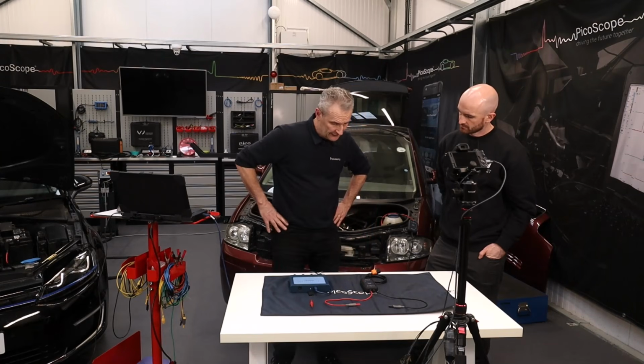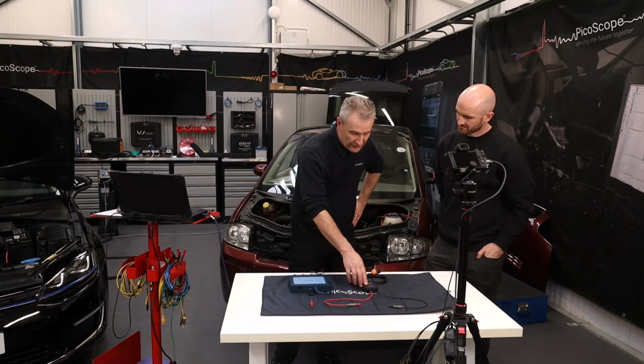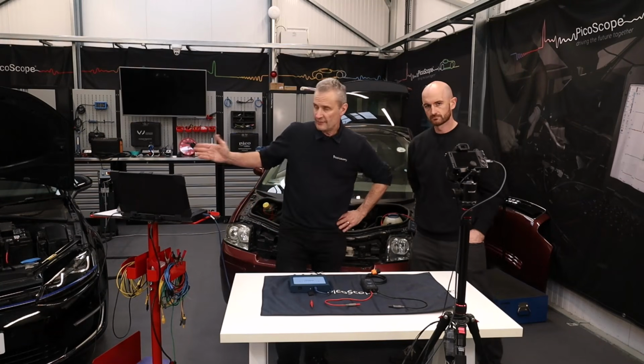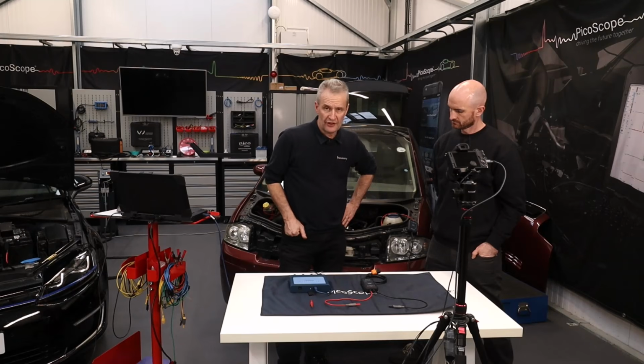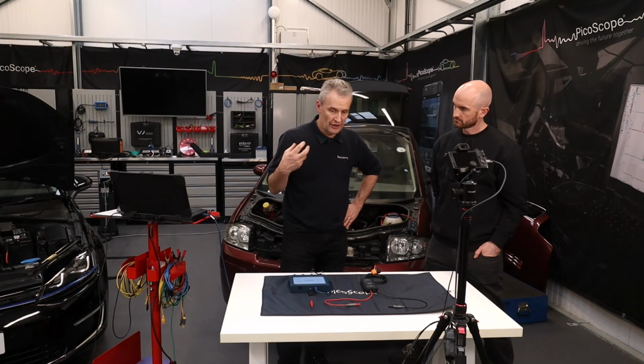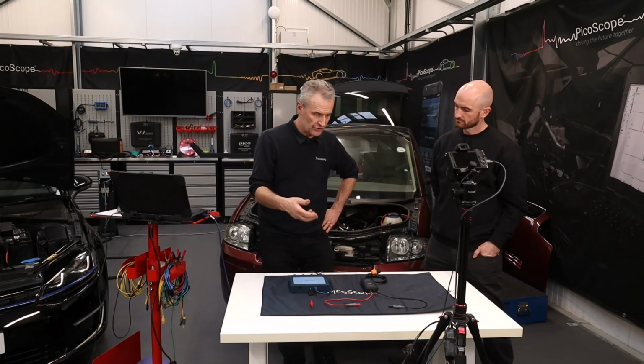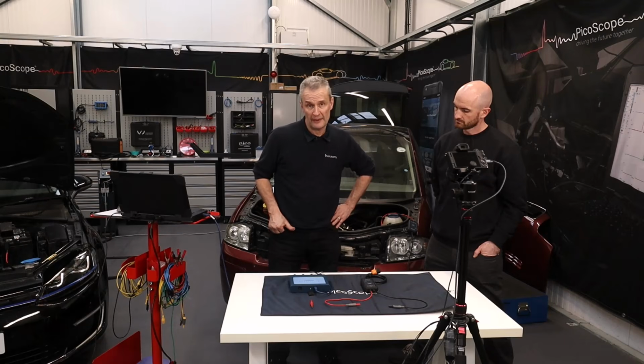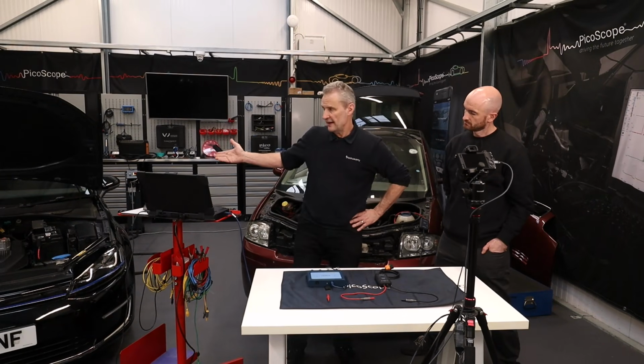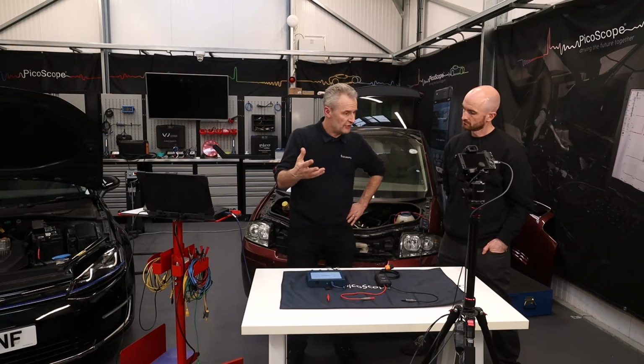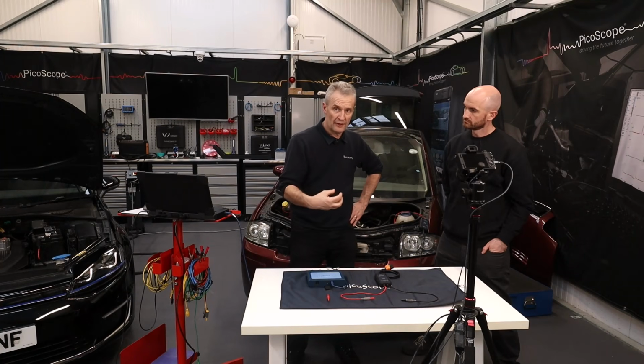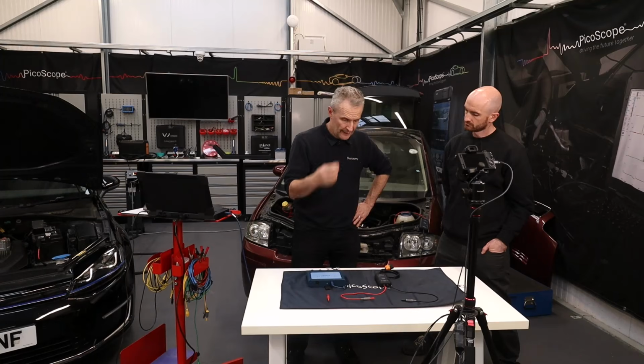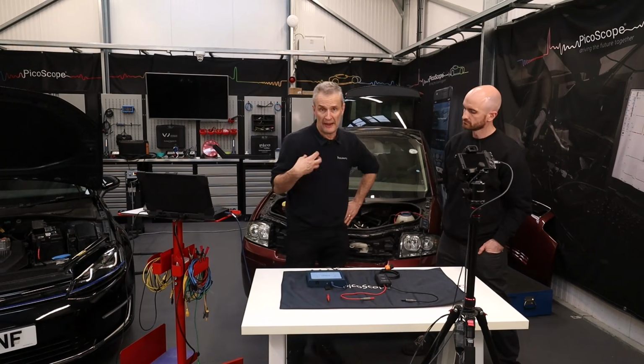It is the probe to carry, and one more thing, as though that wasn't enough, it is cat rated as well. So all of a sudden when we start measuring electric vehicles, cat rating comes into play to protect us from transient voltages. That's all about voltages that, from outside sources, when you're connected to the grid, could actually influence or affect your test equipment and ultimately the user. For example, we're connected to the mains and we're charging, and for whatever reason there's a lightning strike that finds its way into the grid. That's now on its way to you. We want that relevant protection between the circuit we're measuring and ourselves and the scope, of course, but ultimately it's about us, isn't it? Hopefully.